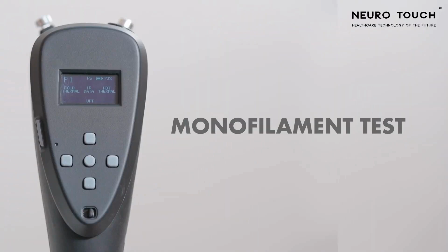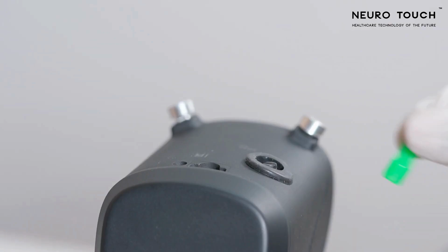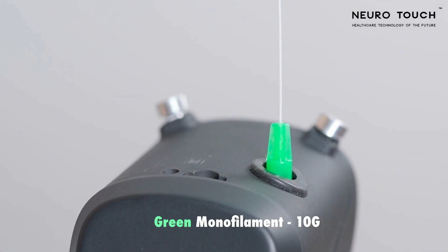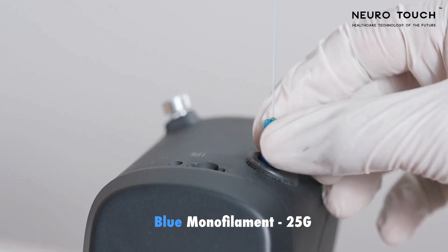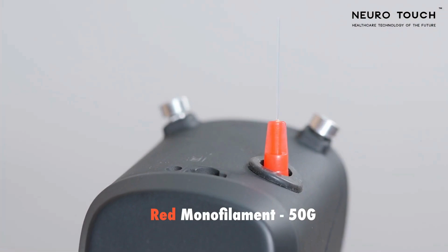Monofilament test. There are 3 types of monofilaments. The green monofilament can record pressure up to 10 grams. The blue monofilament can record pressures up to 25 grams. And with the red monofilament, you can record the pressure of up to 50 grams. Click the up key to start the monofilament test.